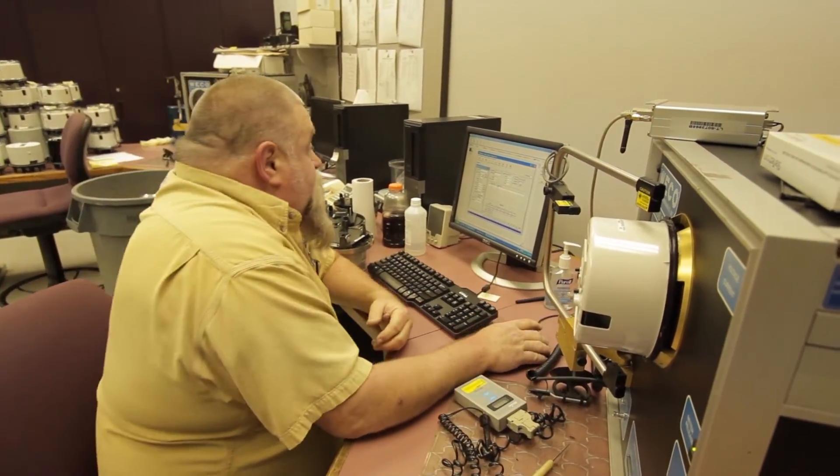While the voltage on the circuit ahead of the transformer might be right in tolerance, because of tap settings in the distribution transformer that weren't set properly when the transformer was originally installed, we were seeing voltages at the customer premise at the meter that were not what we expected at all.